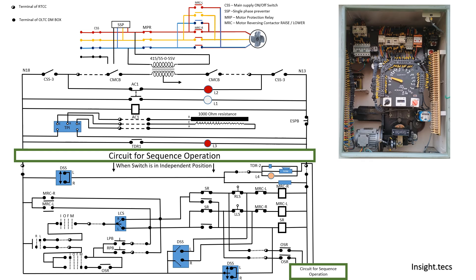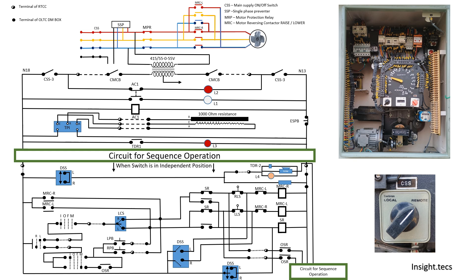Inside the DM box in the OLTC we have a local and remote switch. Whenever local is selected, the operation will be done from the OLTC DM box itself and this path of wiring will be selected for the power flow. Whenever remote is selected, the operation will be done through the RTCC panel and power will flow through that path.